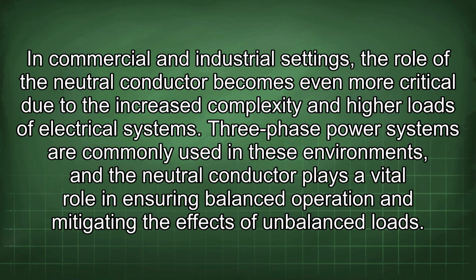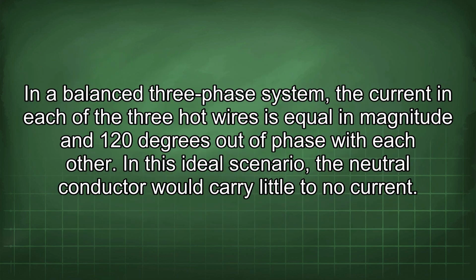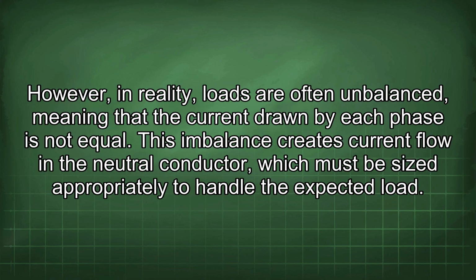Three-phase power systems are commonly used in these environments, and a neutral conductor plays a vital role in ensuring balanced operation and mitigating the effects of unbalanced loads. In a balanced three-phase system, the current in each of the three hot wires is equal in magnitude and 120 degrees out of phase with each other. In this ideal scenario, the neutral conductor would carry little to no current. However, in reality, loads are often imbalanced, meaning that the current drawn by each phase is not equal. This imbalance creates current flow in the neutral conductor, which must be sized appropriately to handle the expected load.